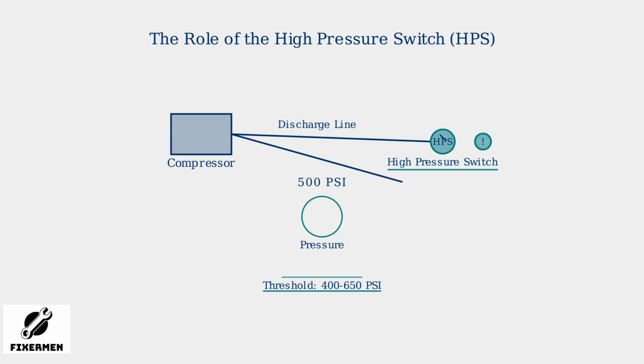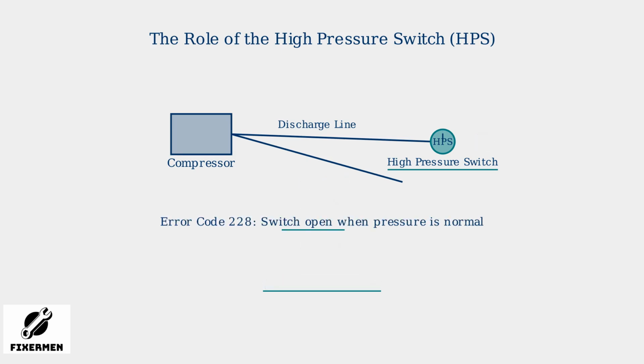When the switch opens, it cuts power to the compressor, stopping operation and preventing potential explosions or refrigerant leaks. Once pressure returns to normal levels around 300 psi, the switch should close again, restoring normal operation. However, Error code 228 occurs when the high-pressure switch remains open even when pressure is not excessively high and the system is not actively cooling.